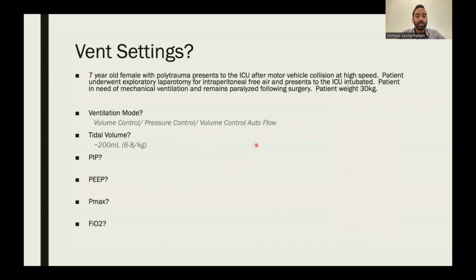Peak inspiratory pressure, probably around 20 to 30 for this patient. 30 is probably a little bit on the higher end. But the peak inspiratory pressure, if you're choosing pressure control, I would set it around 20, see what tidal volumes we achieve, and we can titrate that way. Again, this is for a 7-year-old, so compliance is a little better. And the risk of barotrauma isn't as high as a neonate. So around 20 is okay to start with, and then titrating up.